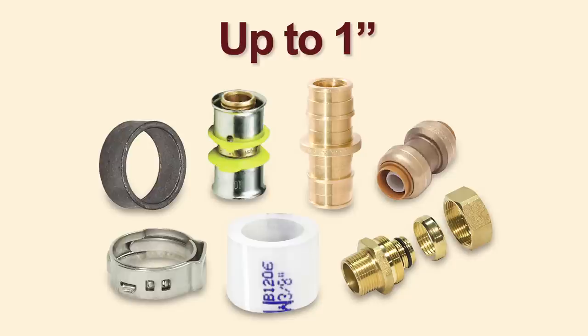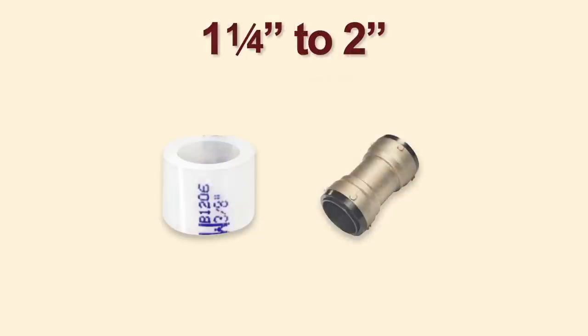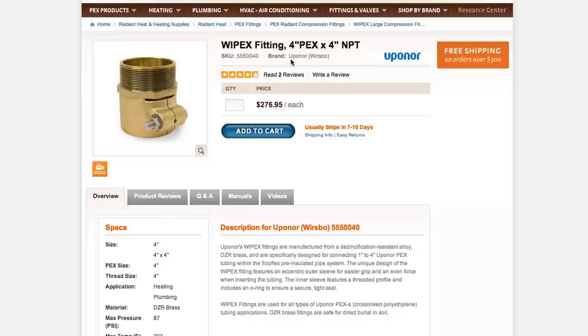All Pex connections work with Aqua Pex tubing up to one inch, but only Pro Pex expansion fittings and SharkBite fittings work with connections from one and a quarter inch to two inches. For sizes larger than two inches, use Uponor's WIPEX fittings.